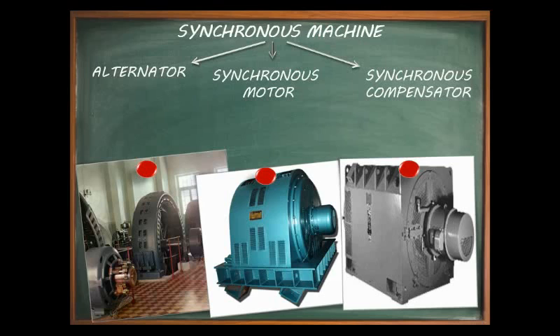A synchronous motor is related to an alternator in the same way as a DC motor is related to a DC generator. In a DC motor, both stator and rotor are supplied from DC supply mains. But in a synchronous motor, the field structure (rotor) is supplied by DC mains, while the armature (stator) is supplied by AC supply. Thus it requires two supplies: one for the armature mains and another for DC excitation of its field windings.